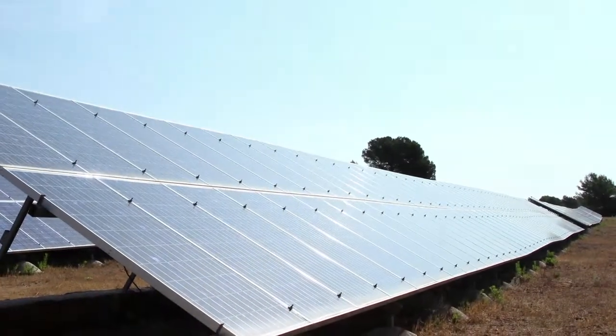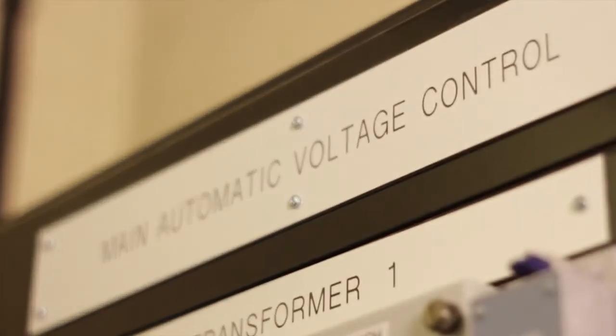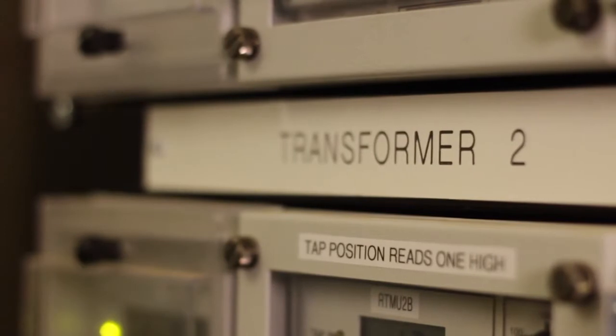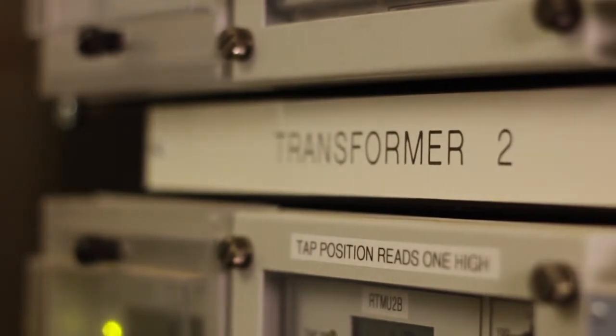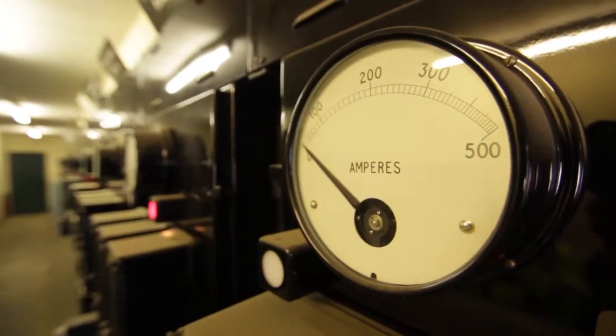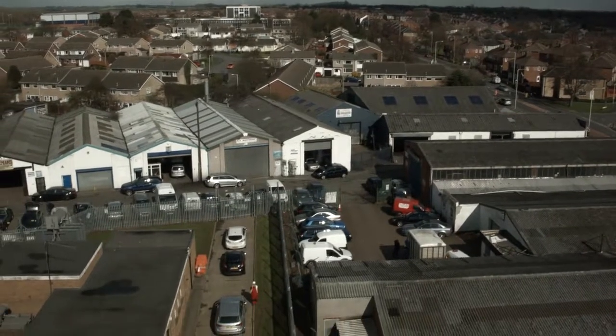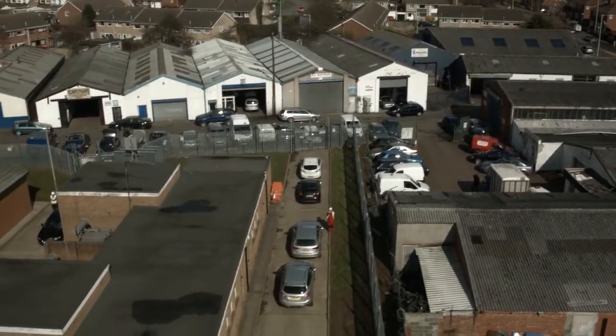The impact of distributed generation on the network can be negative for voltage control. Traditionally, for voltage control, you're only measuring the transformer load current, for example. Most conventional voltage control is essentially looking at your feet. So we have big transformers at big sites that are maybe feeding 10,000 customers, and the voltage it's managing, the voltage it's looking at, is the voltage at that major site.